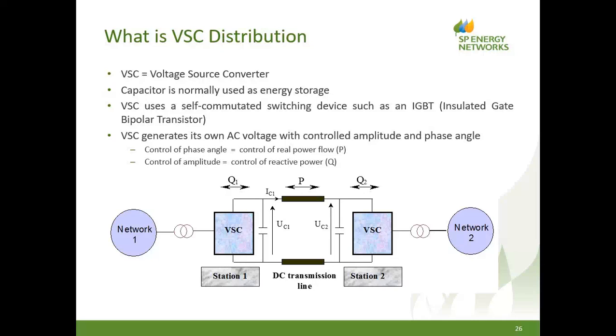The voltage source converter itself uses self-commutating switching devices. These days we use insulated gate bipolar transistors, IGBTs. There are other devices available, but that is quite commonly used. These are fairly standard industrial switching devices. So again, they're not very special for DC applications. But it does give us the ability to turn a DC voltage into an AC voltage, i.e. that we're building an inverter.